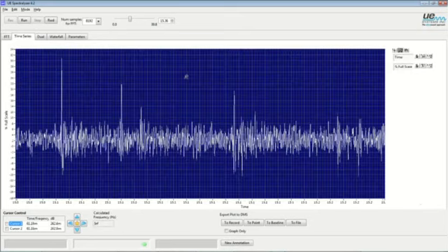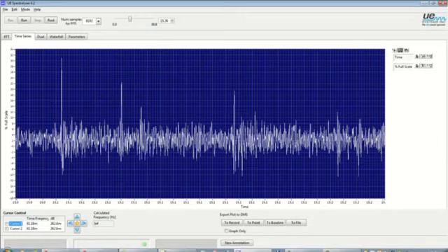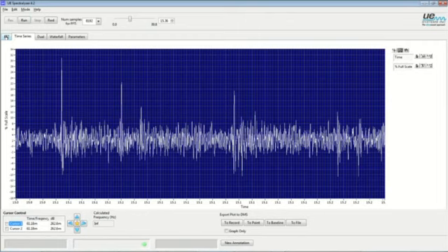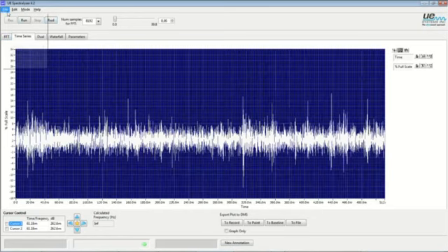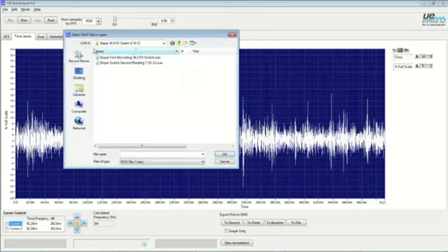When I come to the time analyzer, I'm looking for both variations in the amplitude as well as differences in the timing where the amplitude deviations take place away from the white noise. So that's one type of event there. The other thing it indicated to us was the degradation over time. I'm going to bring up the second recording of that same 34 kV switch.